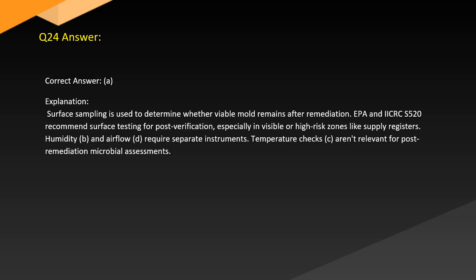Answer. Correct answer: A. Explanation. Surface sampling is used to determine whether viable mold remains after remediation. EPA and IICRC recommend surface testing for post-verification, especially in visible or high-risk zones like supply registers. Humidity (B) and airflow (D) require separate instruments. Temperature checks (C) aren't relevant for post-remediation microbial assessments.